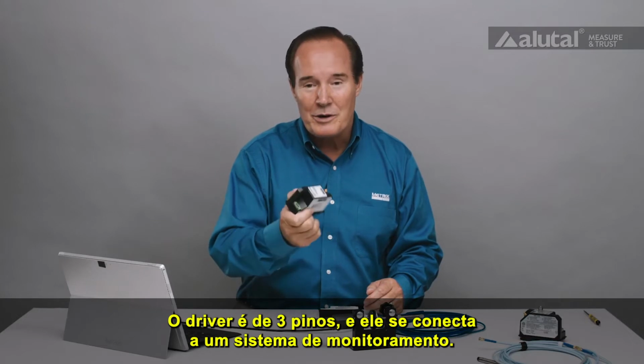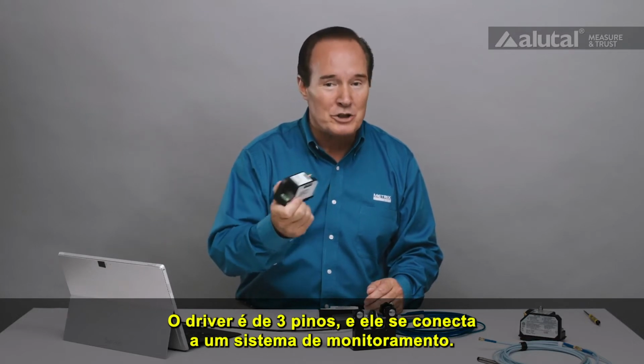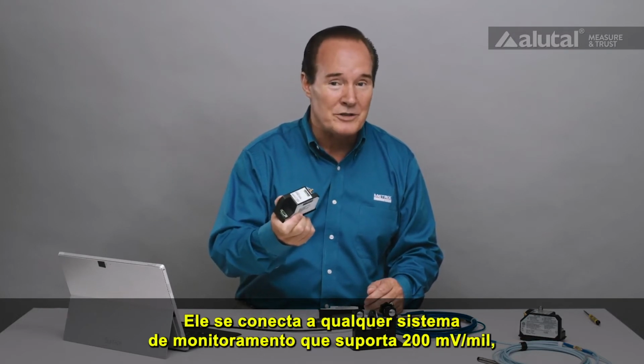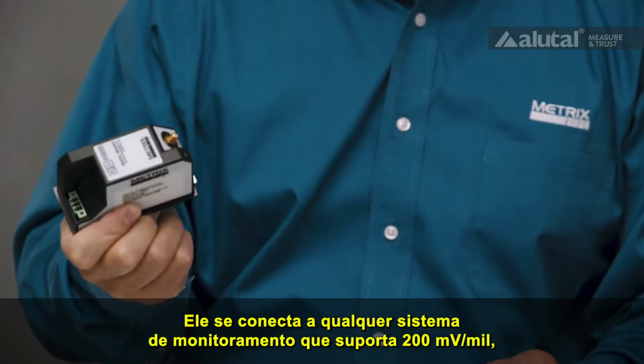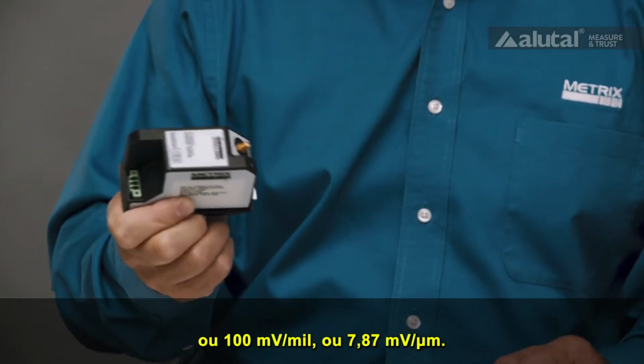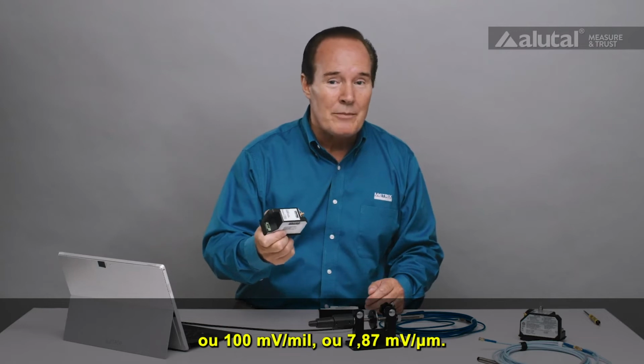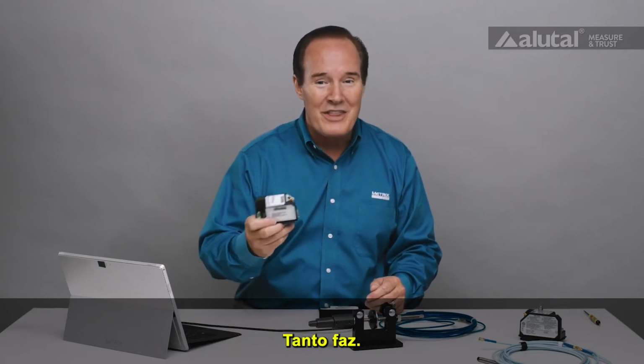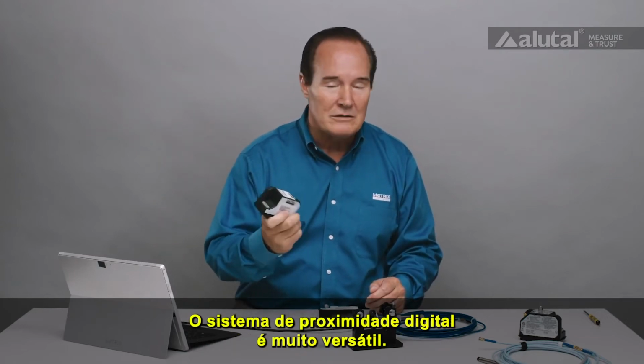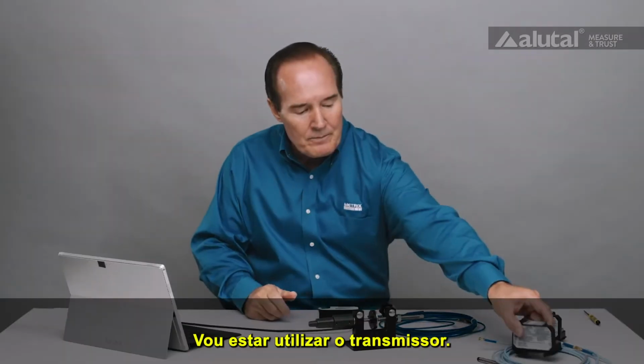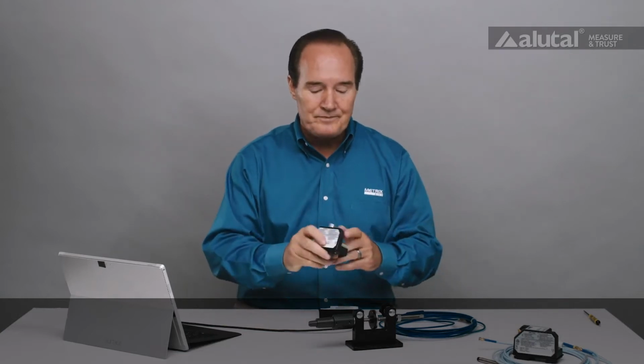So the driver is a 3-pin driver, and that would go to a monitoring system. And really anybody's monitoring system that can take 200 millivolts per mil or 100 millivolts per mil or 7.87 millivolts per micron, whatever that is. So the digital proximity system is very versatile. This is our driver. Now, I'm going to be using the transmitter.